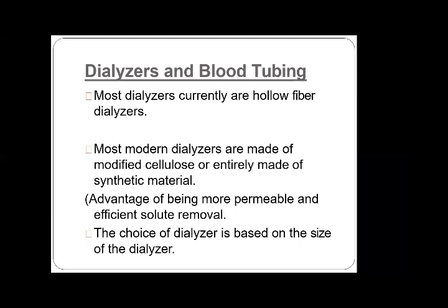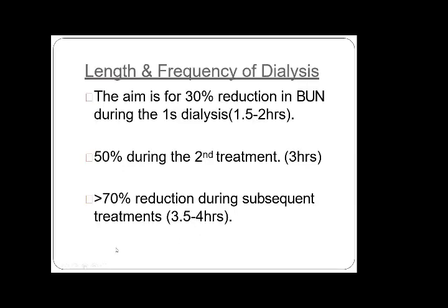So, the dialyzer and the blood tubing. Most dialyzers currently are hollow fiber dialyzers. Most modern dialyzers are made of modified cellulose or entirely of synthetic material, with the advantage of being more permeable and giving efficient solute removal. These are specialized filters used for hemodialysis, and the choice of dialyzer is based on the size of the dialyzer. And then you have the length and frequency of dialysis.